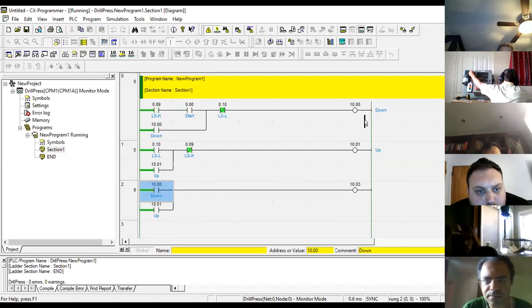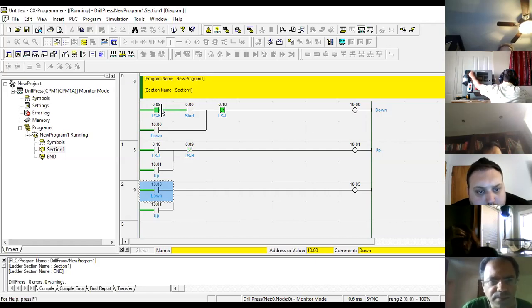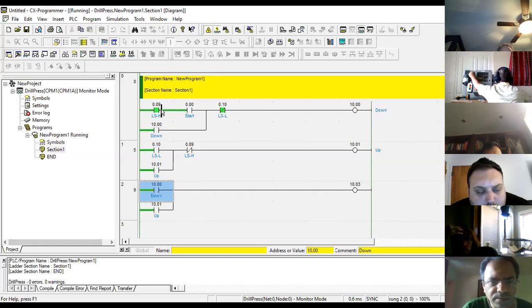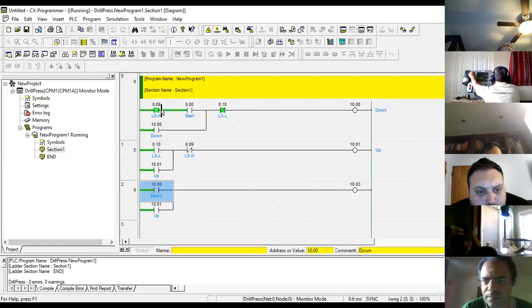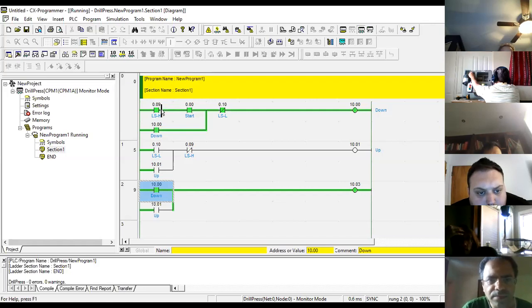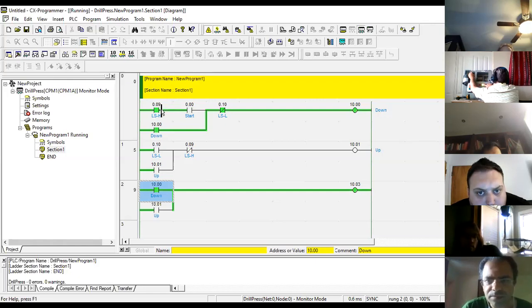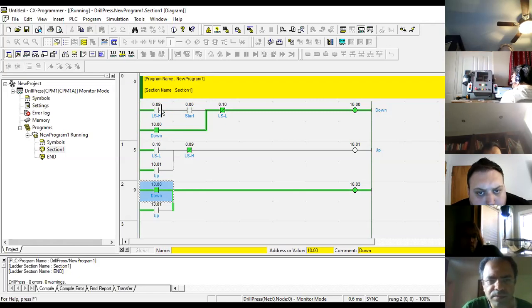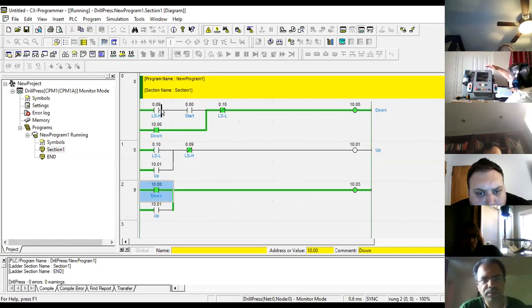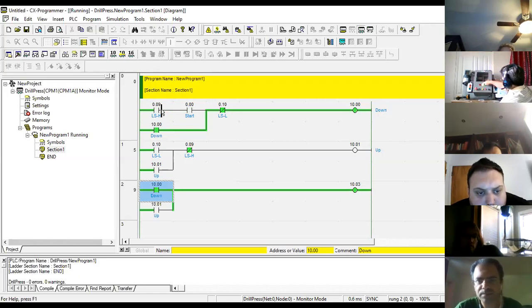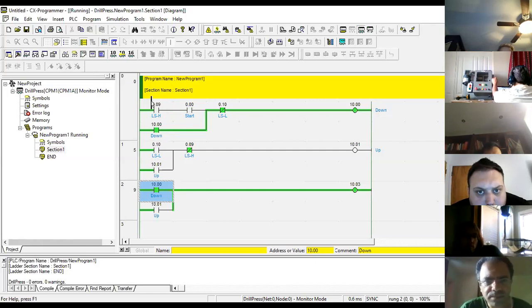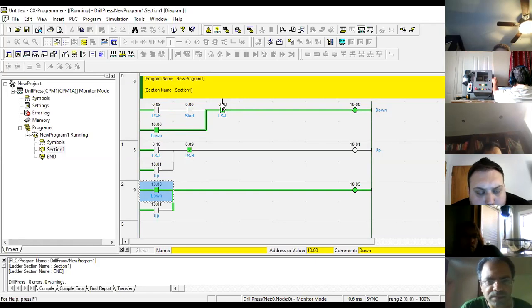We'll try limit switch. Have a look at the screen here. When I activate my limit switch, this guy here is closed. I'm in the upper position. I'm going to press start. I'm pressing start, which means that it's coming down. Look, my yellow light I said was my drill. My drill is turning. When I let go of the limit switch, it has to continue right now. The machine is going down and it's drilling. When I press the lower limit switch here, when I activate this lower limit switch, it's going to deactivate my down and it's going to activate my up.